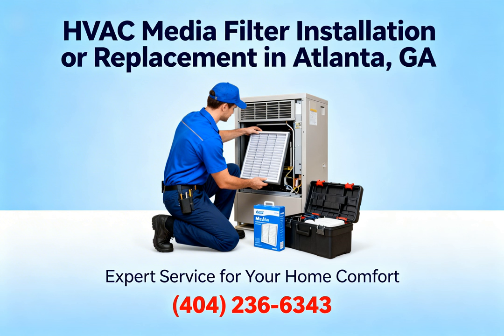Sure. But if you unfold a 5-inch deep pleat media filter, it provides up to 40 times the filtering surface area. 40 times. Yeah, and that massive increase in surface area fundamentally changes the fluid dynamics of how the system cleans the air. Well, when you have 40 times the space for air to pass through, you can utilize a significantly denser, tightly woven filtering material without just creating a barricade. Okay, that makes sense.